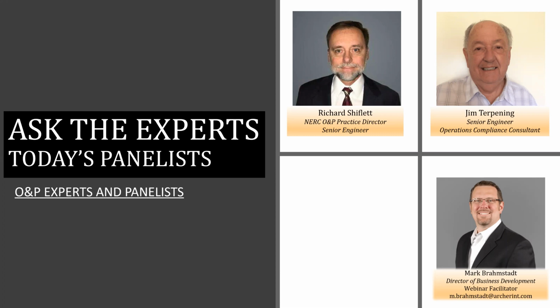A facility refers to all the components that comprise a given facility. So if it's a transmission facility, it will be the terminal equipment and the transmission conductors. If it's a generation facility, it'll be the generator or generators up to and through the generator step-up transformer and the interposing equipment. And you'll have an overall rating we refer to as the facility rating for that given capital F facility. Then there will be the equipment ratings that will be detailed as part of that facility.